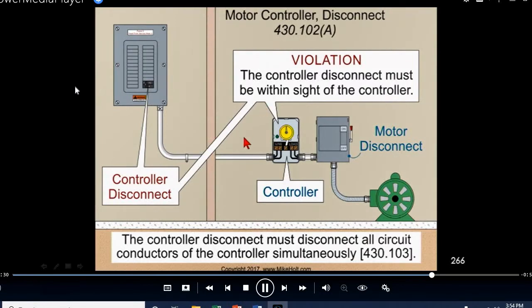Now, this is a violation because this is the controller of the time clock, and this disconnect is not within sight of that controller. The controller disconnect must disconnect all circuit conductors of the controller simultaneously. Here's my controller, and the violation here is that it's not within sight.